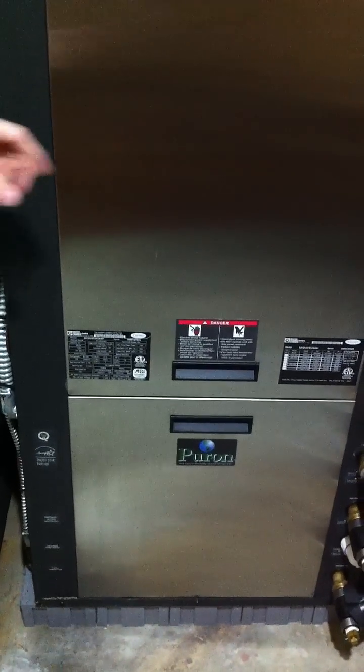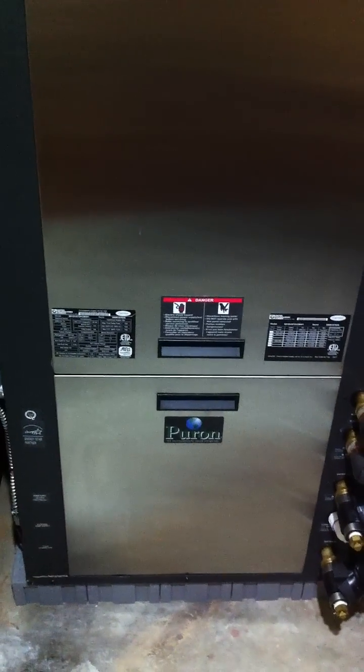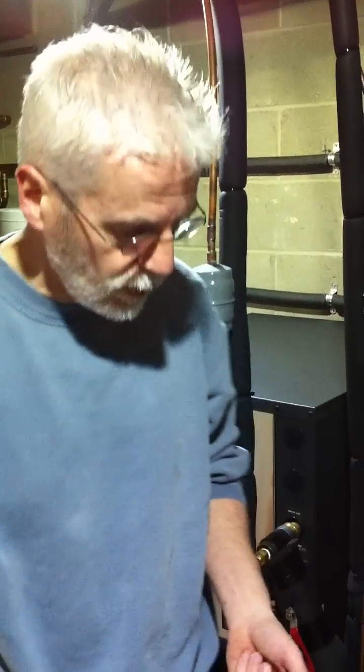So we have a coil in there, and right next, molded next to that coil, is another coil with refrigerant. That refrigerant passes by right as the water passes by and picks up a little bit of the water's temperature — about typically four to six degrees of temperature we get out of the water.